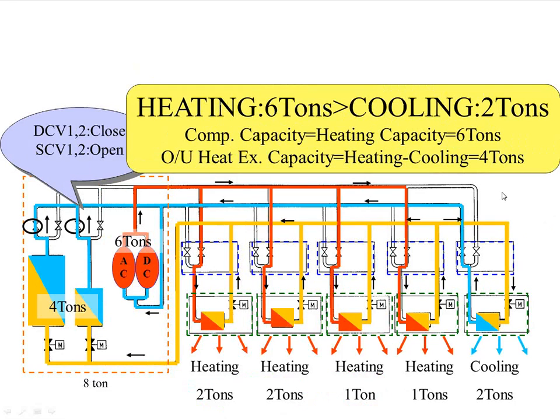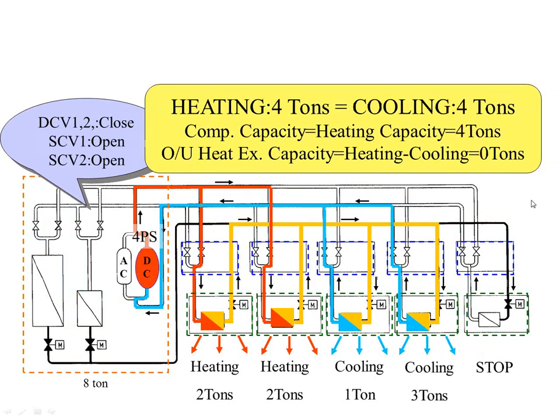And likewise, if I have more heating zones than cooling zones, then it works a little bit differently. In this case, I have 1, 2, 3, 4, 5, 6 tons of heating, and I need 2 tons of cooling, right? So my condensing unit goes into the heating mode. I'm grabbing 4 tons of heat from the outdoor air. I'm pumping 6 tons of compression to move those 4 tons into my zones. And I'm grabbing my other 2 tons of heat from my zone that wants cooling. So I still have 6 tons of cooling going on and 6 tons of heating going on, just choosing which zones I dump them into. So I'm getting a total of 8 tons of heating and cooling effect for the heat rejection price of 4 tons, for the compressor pumping power of 6 tons.